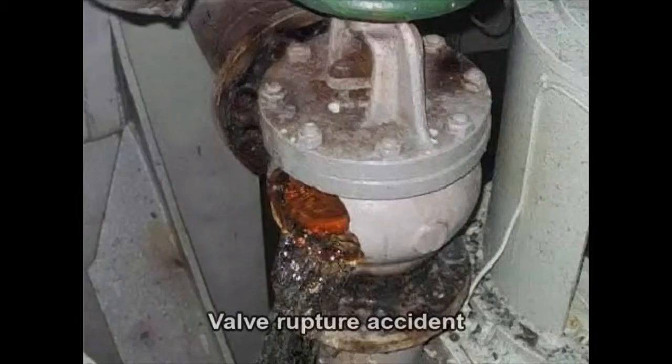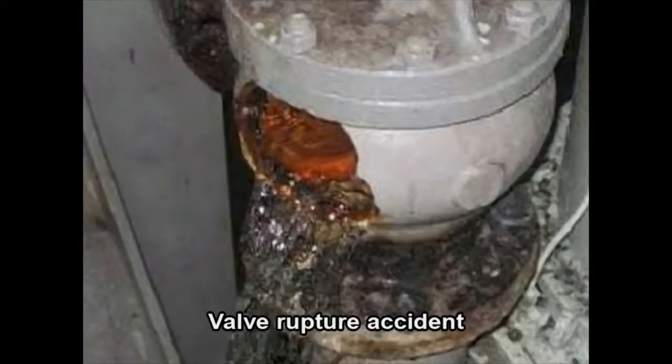This is an example of an accident caused by valve rupture. In this accident, corrosion in the valve body, combined with sudden pressure change due to pump stopping, ruptured the valve body during operation to produce a hole in it.